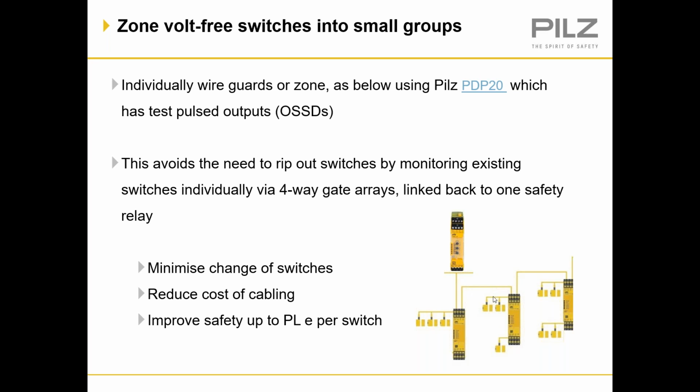So instead of removing all your existing volt-free switches, you can add these PDP-20 units to your machine, which will minimize the changeover of switches, reduce your cost of cabling, and improve safety up to PLe per switch, as they have 99% diagnostic coverage.